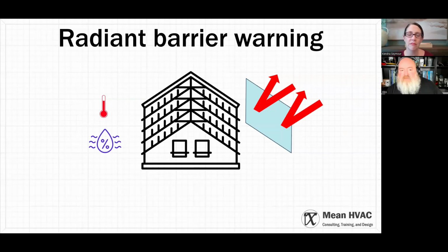And the ducts themselves have a surface temperature. If that surface temperature gets below the dew point of the air in the attic, you start to get condensation and dripping water on your ceilings. So lowering the temperature in the attic, which has nothing to do with humidity, will lower the surface temperature of those ducts and can actually cause a humidity problem.